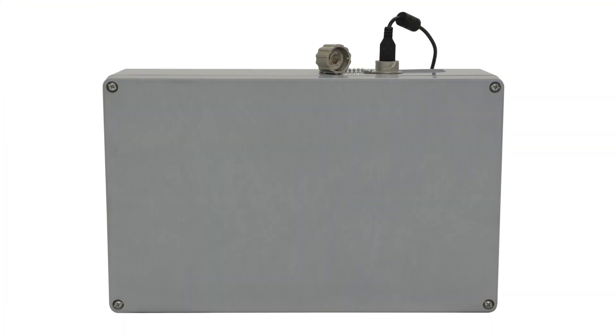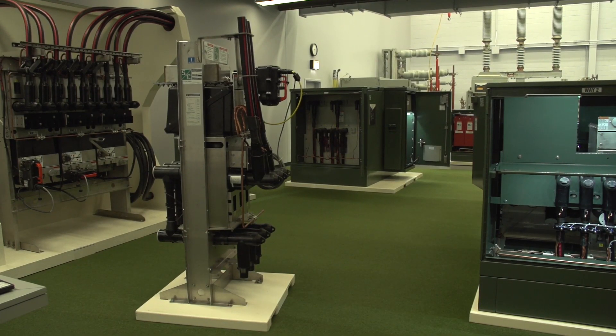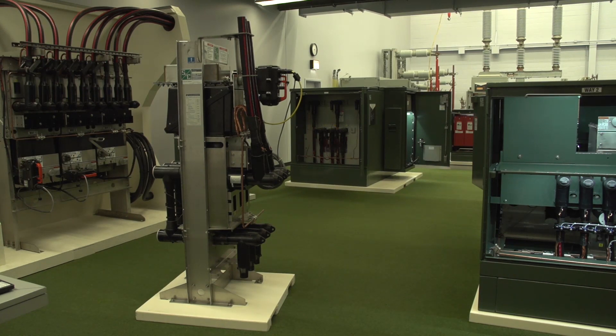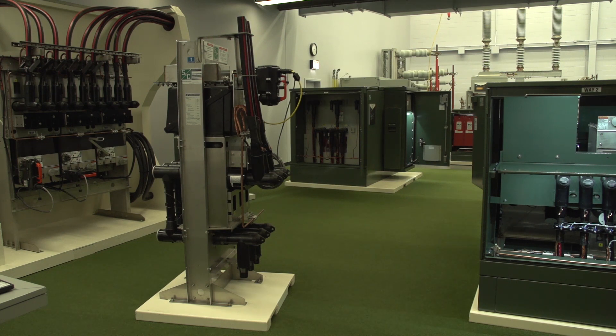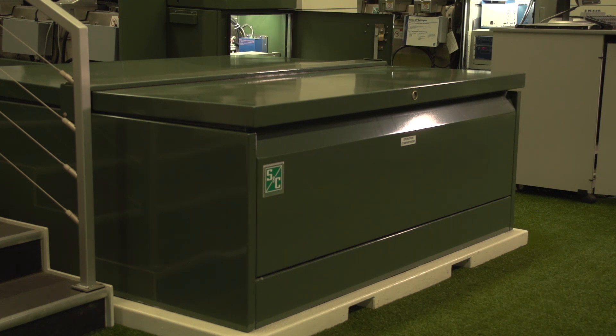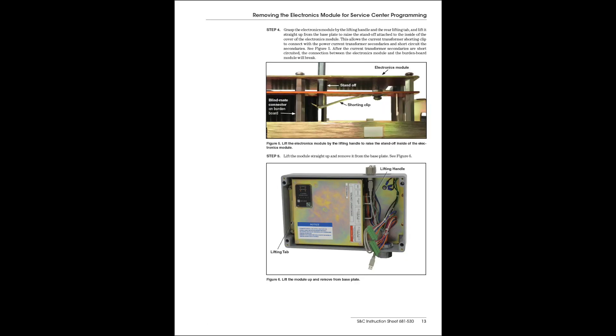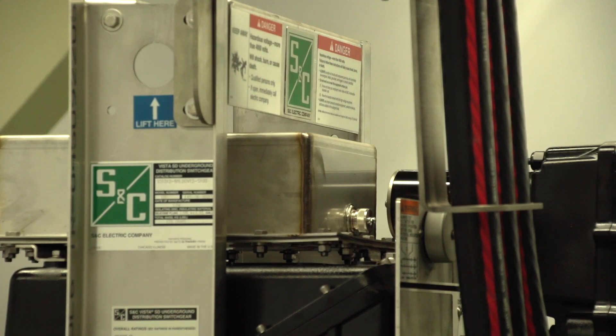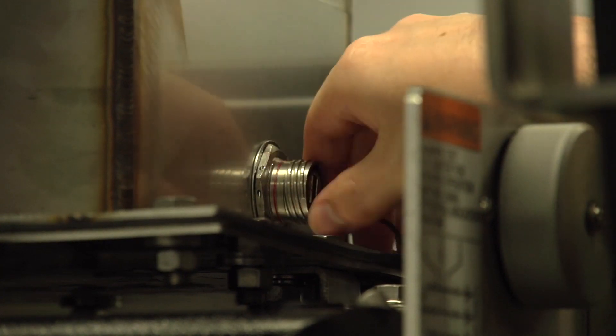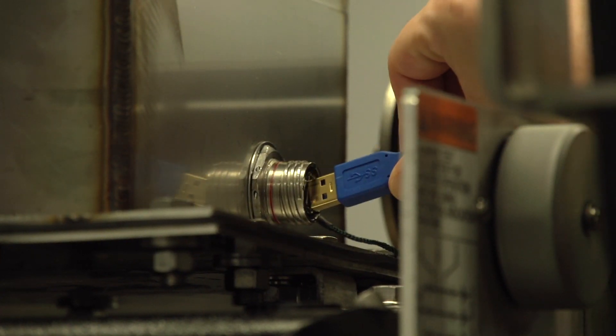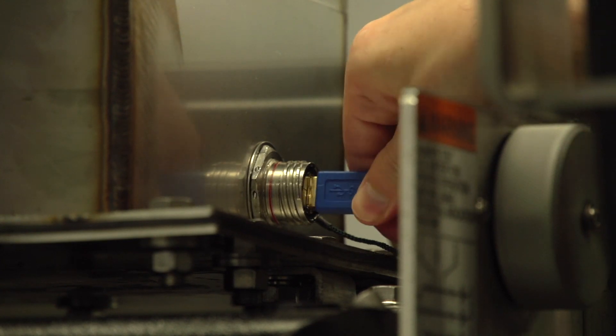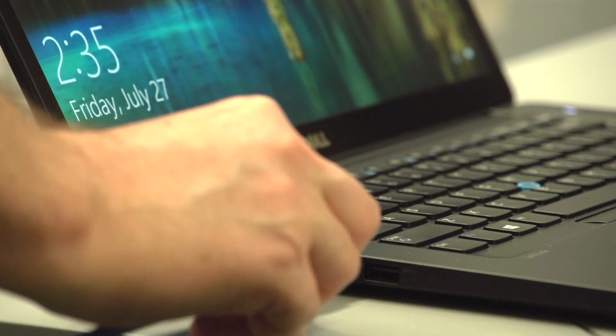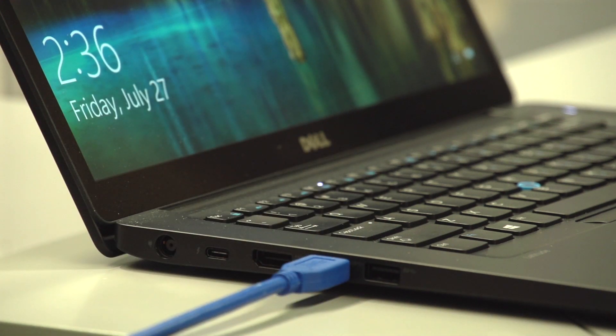The overcurrent control is housed in an enclosure mounted on the operation side of the switchgear. For undercover style and vault-mounted style Vista and Vista SD switchgear, the enclosure is fully submersible, and the control should not be removed for bench programming. For pad-mounted and dry-vault style Vistas, the overcurrent control's electronics module is removable for bench programming. The written instructions give a lot more information on removing the control from the enclosure. Here's the USB port on the control. Just take the cap off and plug in a common USB-A type cable. The other end plugs into a PC.